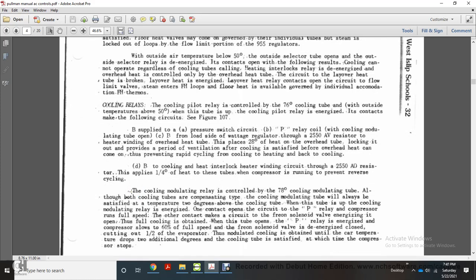The cooling pilot relay is controlled by the 76-degree cooling tube, active when outside temperature is above 50 degrees Fahrenheit. When the cooling pilot relay is energized, its contacts make the following circuits: B is supplied to: (a) the pressure switch circuit; B — the P relay with the cooling modulating tube open; C — from the load side of the watt regulator through the 2550 AV resistor to the heater winding of the overhead heat tube. This places 28 degrees of heat in the overhead heat tube, providing a period of ventilation after cooling is satisfied before overhead heat can come on.